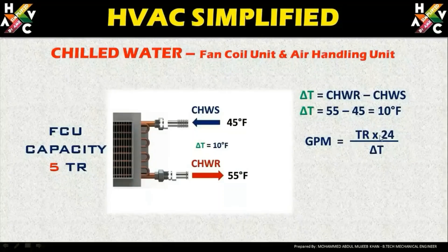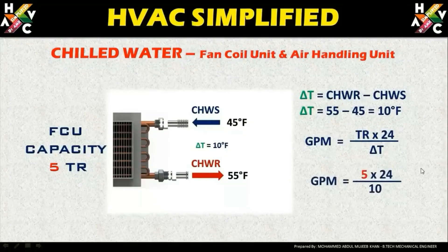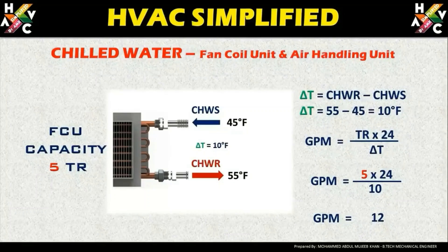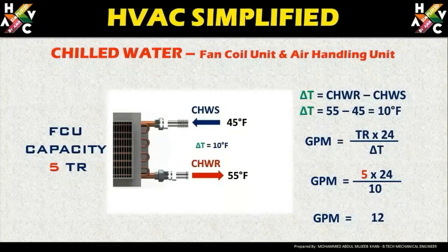Now we apply the GPM formula: GPM equals TR multiplied by 24 divided by delta T, which is 5 tons multiplied by 24 divided by 10 (the delta T). So the GPM for this 5-ton fan coil unit based on these parameters is 12 GPM. Based on this formula, any chilled water supply parameters can be derived.